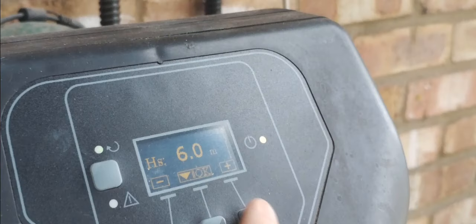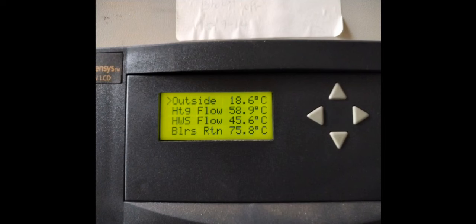And this is another site where I'm just checking the head pressure on a DAB pump. I was increasing the head pressure from 6 meters to 7. The reason I was increasing is because the heat wasn't really getting away from the header area on the boiler, and not getting away on the variable temperature. And the pumps were sometimes at like 1-2 meters of head, but it needed to be more like 6-7. So I made an adjustment and changed that.